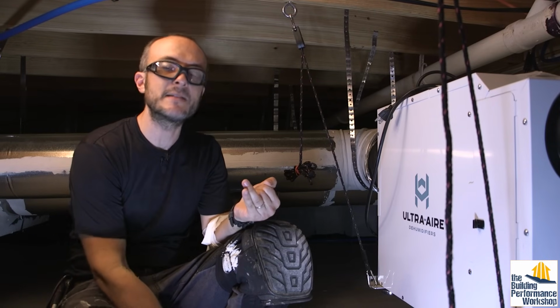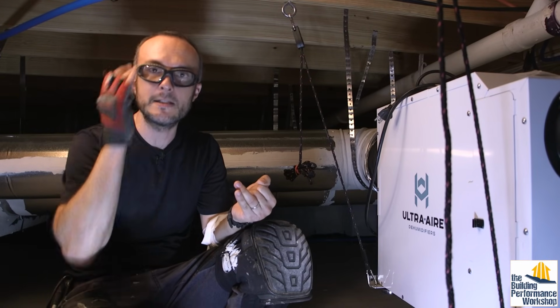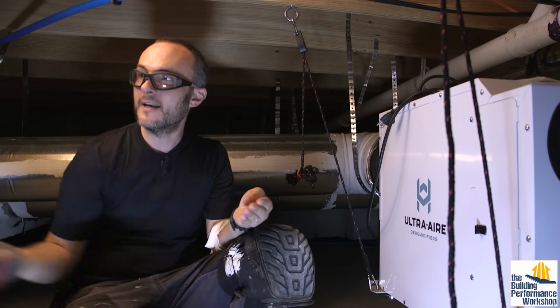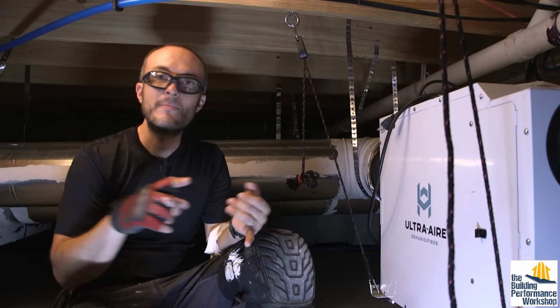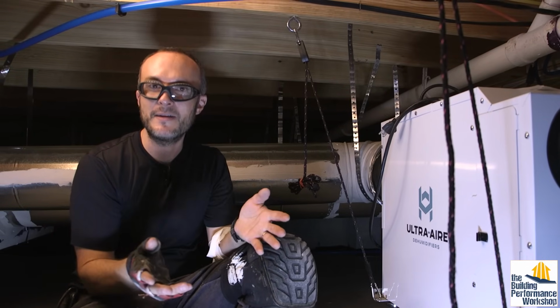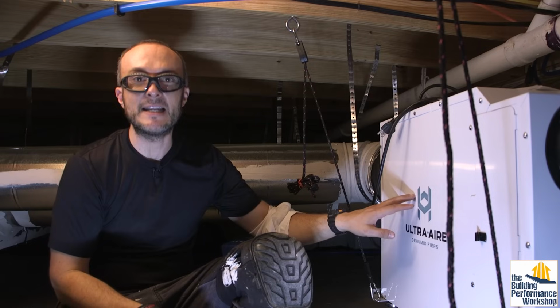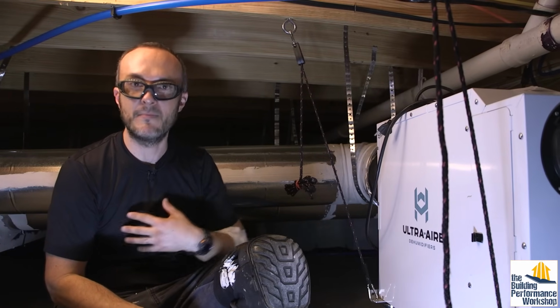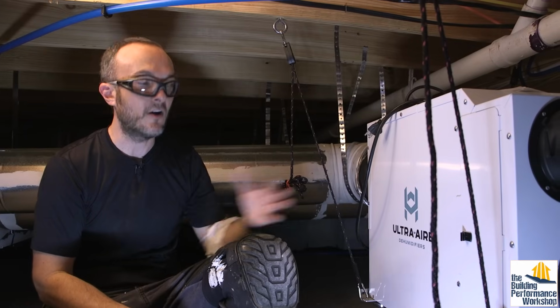Your HVAC system is smaller than it's ever been before in new homes. Therefore, it's going to dehumidify less. And it's going to run less in general because we've lowered the load by air sealing and insulating the homes, as we already mentioned. You need to have a dedicated dehumidification solution in basically every new home, is what a lot of people, including me, are agreeing on.